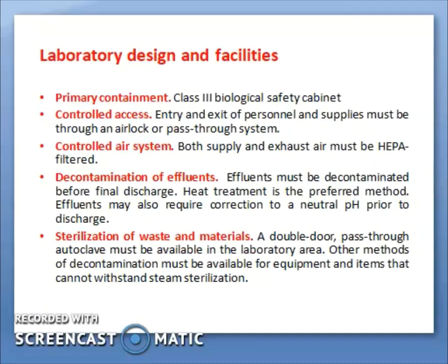The controlled air system, including both supply and exhaust air, must be HEPA filtered. The effluents must be decontaminated before final discharge. Heat treatment is the preferred method. Effluents may also require correction to a neutral pH prior to discharge. For the sterilization of waste materials, a double-door pass-through autoclave must be available in the lab area. Other methods of decontamination must be available for equipment and items that cannot withstand steam sterilization.